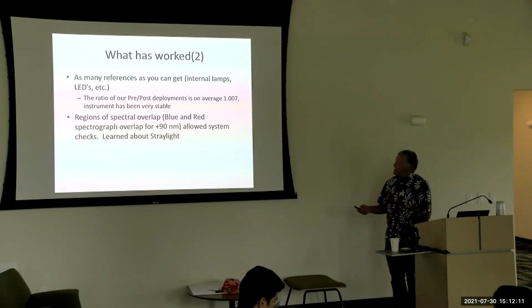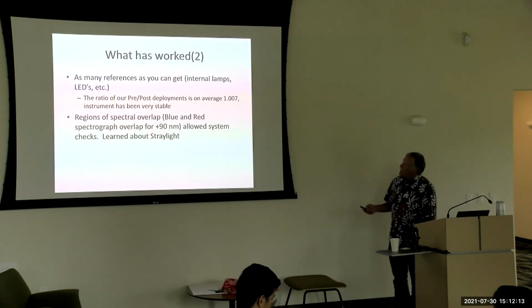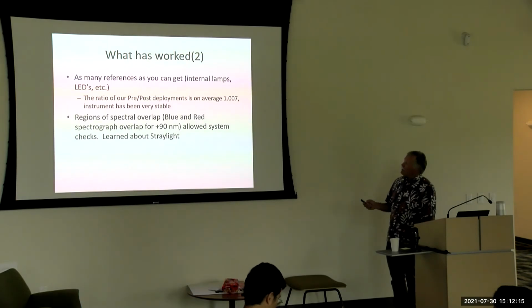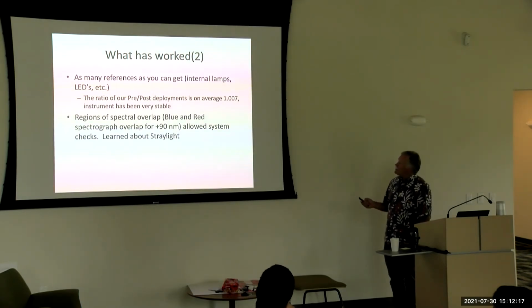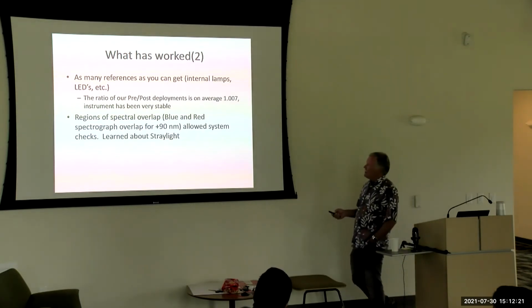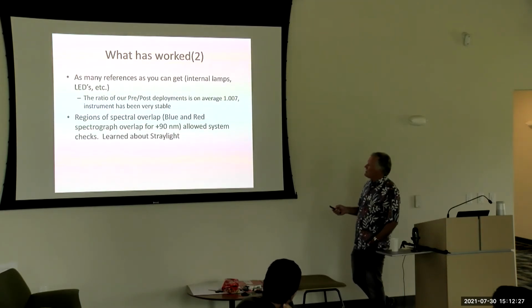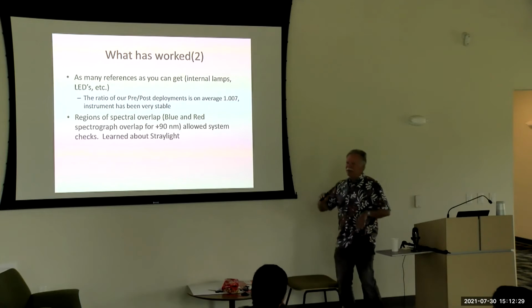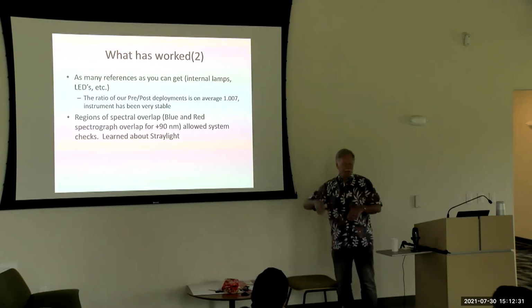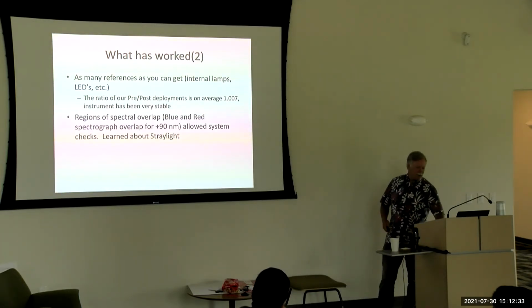Having extra internal lamps is good. Our pre- and post-deployment average is about 0.7%, so the instrument is really stable. The region of spectral overlap was really useful. It allowed us to see stray light and to check between the two spectrographs for problems.